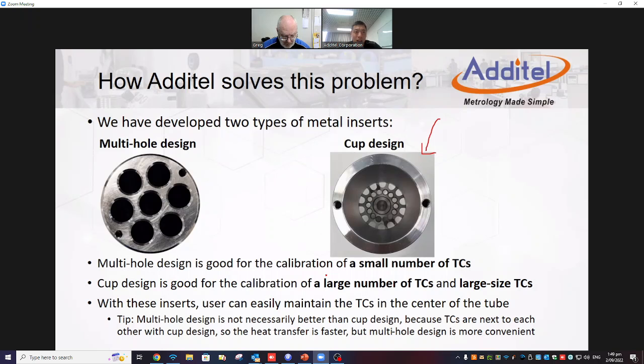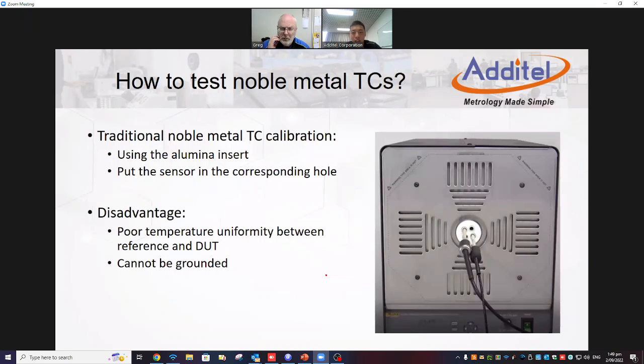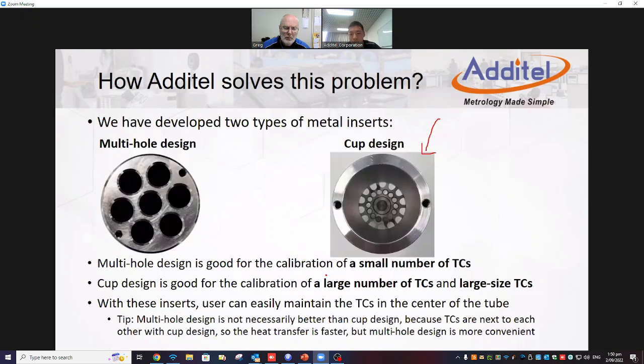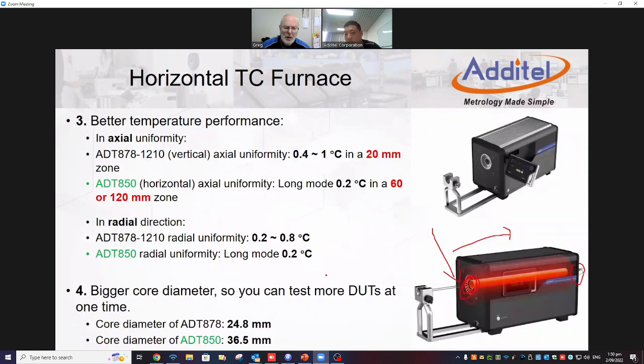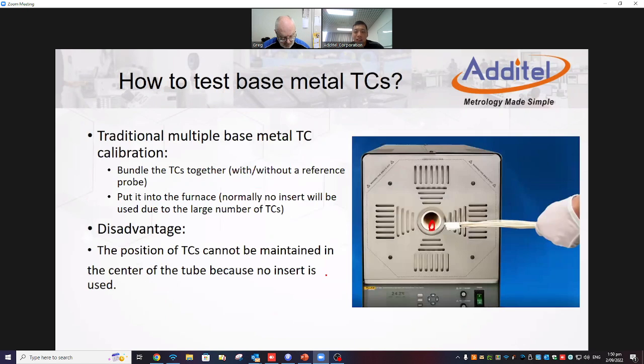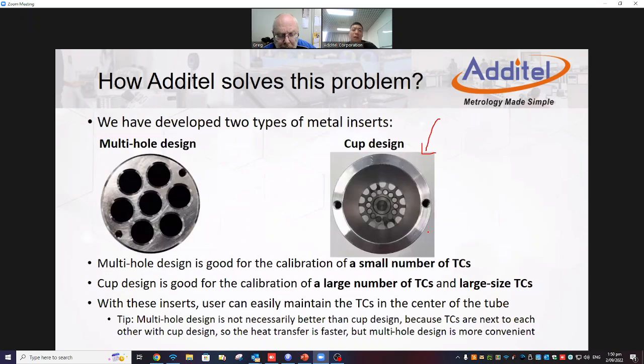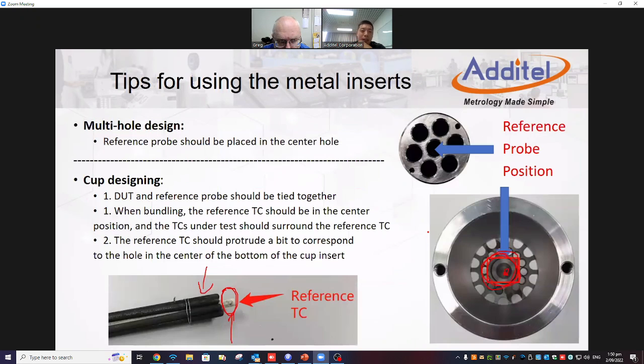They can use the bare hole, or they can use the furnace without the insert. For example, with a pretty big bundle where the cup design doesn't have enough diameter, no problem - they can put the entire bundle inside the furnace. But just like the traditional way, they may have a problem where the entire bundle sits at the bottom of the furnace core. If they have a really high accuracy requirement, that could be an issue, but I think most industrial customers are okay with that.